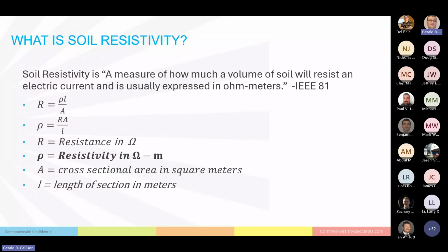Now, what is soil resistivity? IEEE 81 gives us a fairly straightforward definition: a measure of how much of a volume of soil will resist an electric current, usually expressed in ohm meters. I put some equations below that. Resistance through a conductor of length L is equal to resistivity times the length L over the cross-sectional area A of that conductor. Resistivity is equal to resistance times the cross-sectional area of the conductor divided by the length. Resistance is in ohms, resistivity is in ohm meters. This just gives you a conceptual understanding of resistance versus resistivity.